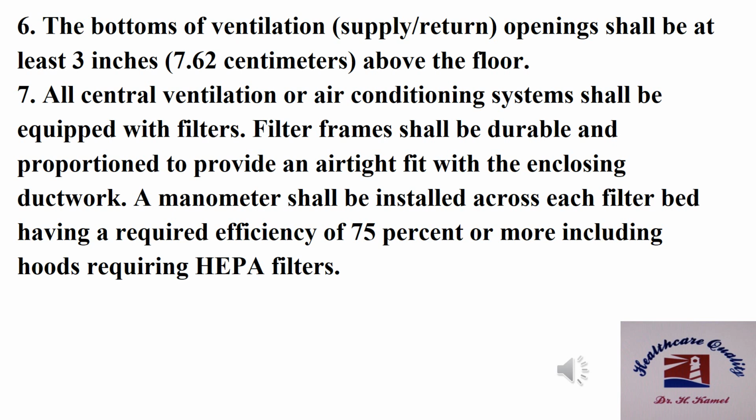A manometer shall be installed across each filter bed having a required efficiency of 75% or more, including hoods requiring HEPA filters.